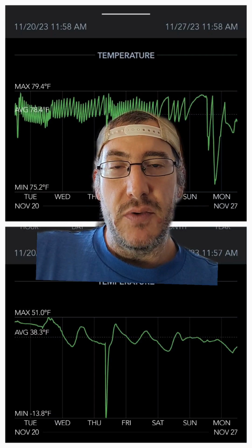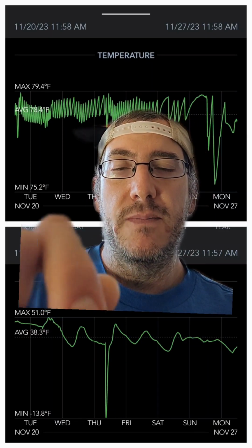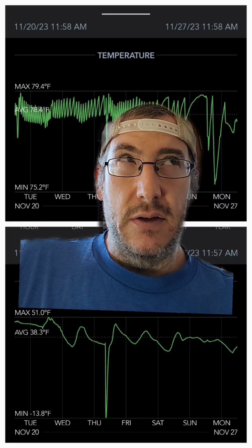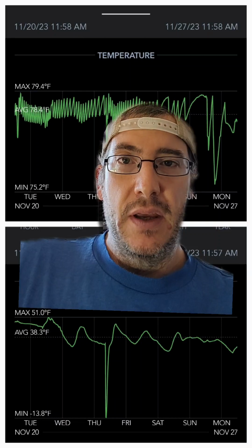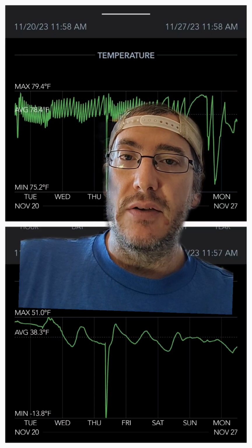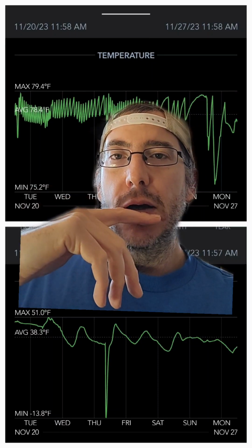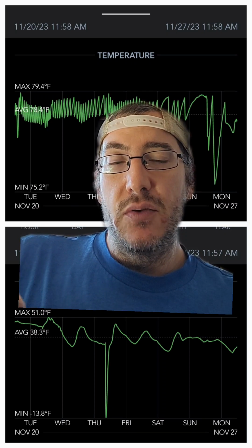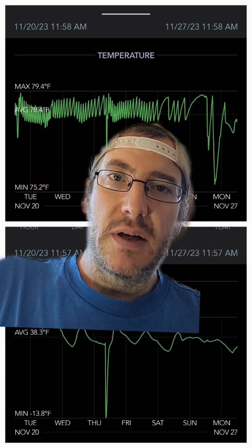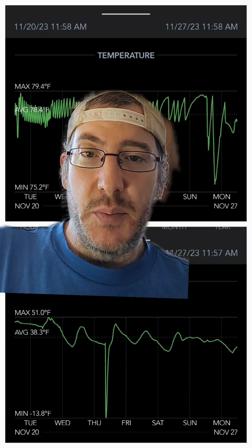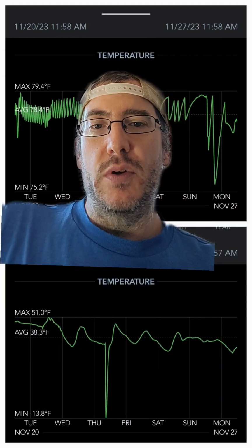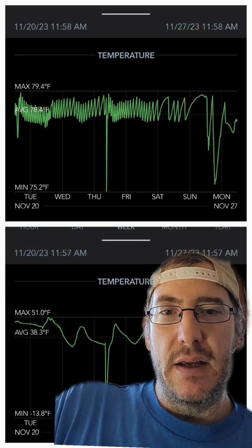temperature gets too high. So right now I have a sensor hooked up to the exhaust fan that, once it reaches, I want to say it's 80 degrees in that section of the room, will turn on and run until it gets back down to 76 at that sensor. And so what that's doing is two things. One, it's keeping the temperature in that range, which we can see here. And when it does pull in that air, it's pulling in this ambient temperature air at the bottom, this air here. So what's interesting, and same issue here with the data at the bottom.